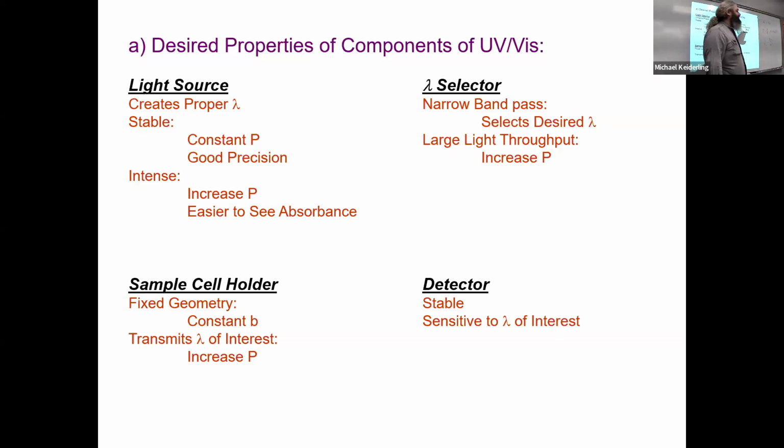Generally, ways that let you select your wavelength nicely will decrease your power, because it's generally done by making slits thinner. So you're literally letting less light through. That's one of the big trade-offs you have to take into account. In general, a narrower band pass corresponds to less light passing through, which means less input power.